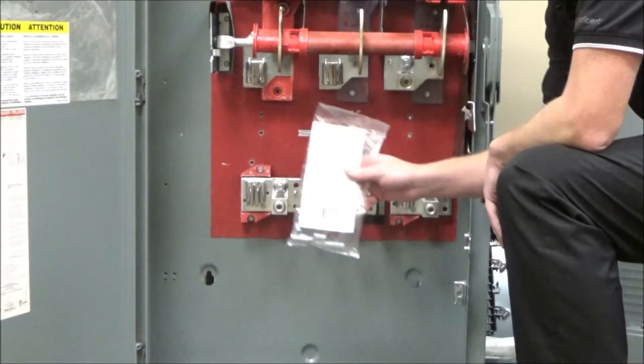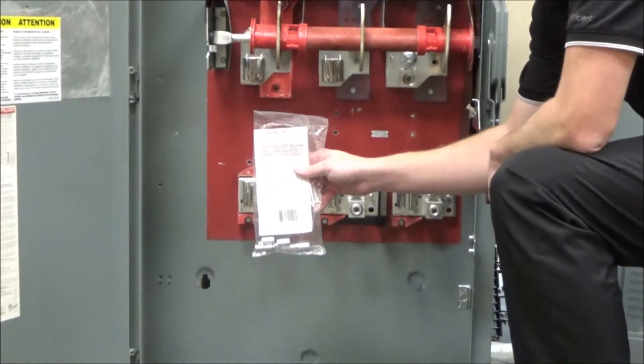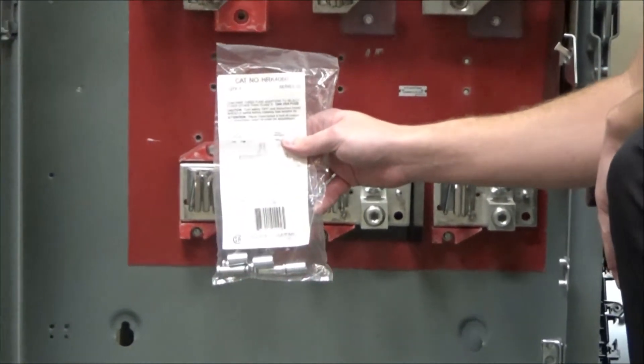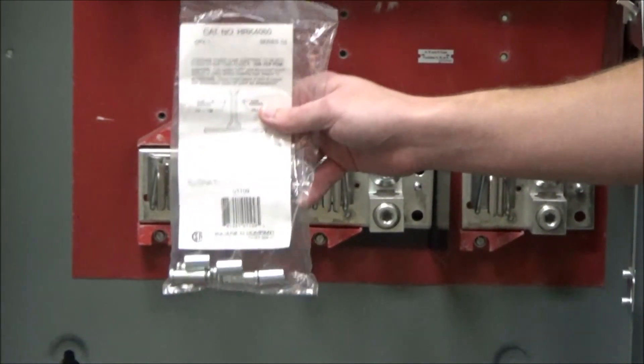In this video we'll be showing you how to install the HRK4060 class R fuse kit into a 400 amp heavy-duty safety switch.